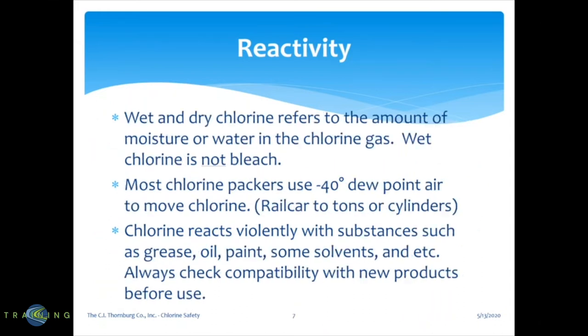Wet and dry chlorine refers to the amount of moisture or water in the chlorine gas. Wet chlorine is not bleach — not sodium hypochlorite. Most chlorine packers use minus 40 degrees dew point air to move chlorine from the rail car to their cylinders or ton cylinders. Chlorine reacts violently with substances such as grease, oil, paint, and some solvents. Always check compatibility with any new products before you introduce them.